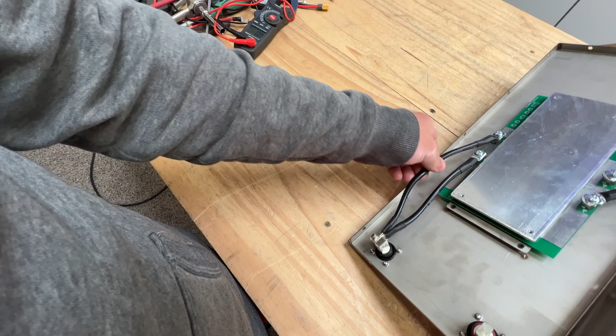They're using 2 wires per terminal, and this is sufficient because this BMS is only rated for 100 amps - that's what the battery is rated at, 1C. The BMS is screwed on the top lid with a big heat sink touching all the MOSFETs. It doesn't use the actual case of the battery to cool it, but it does have a large, maybe 3/16 thick, aluminum plate to dissipate heat created when loading this with 100 amps.